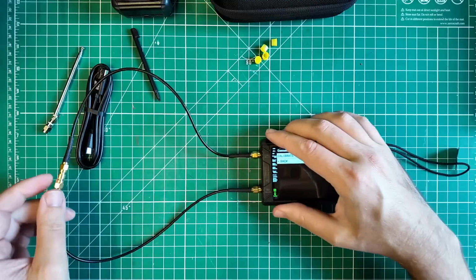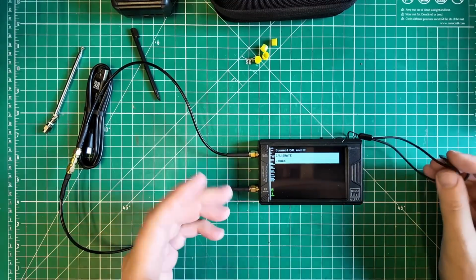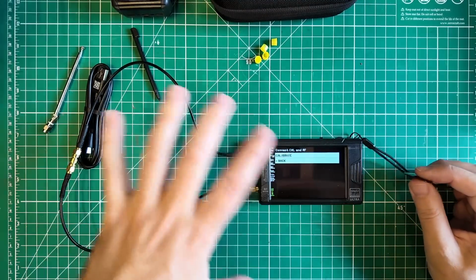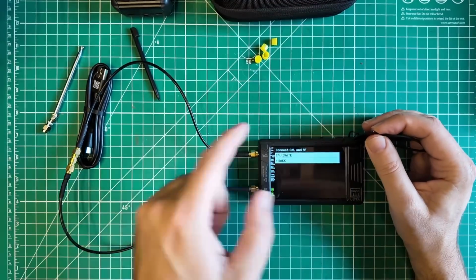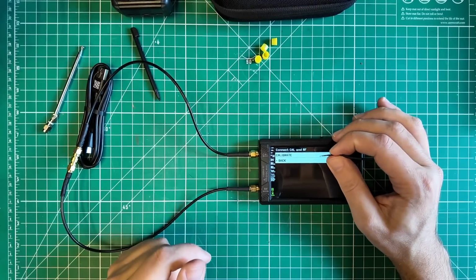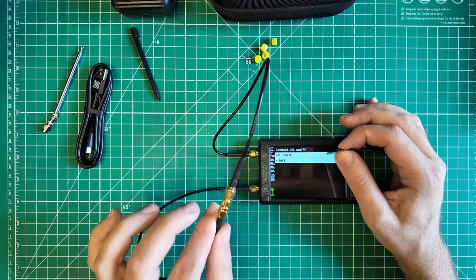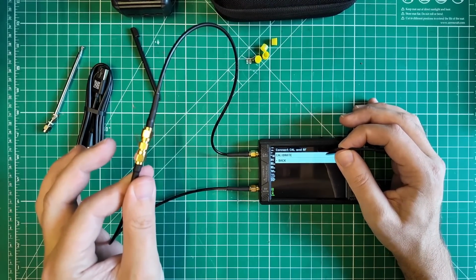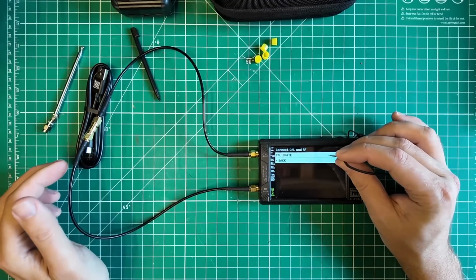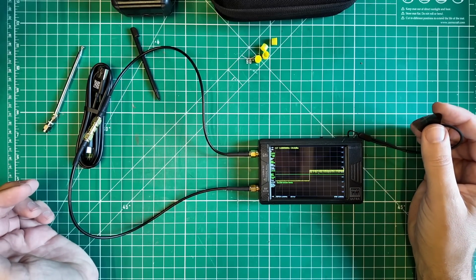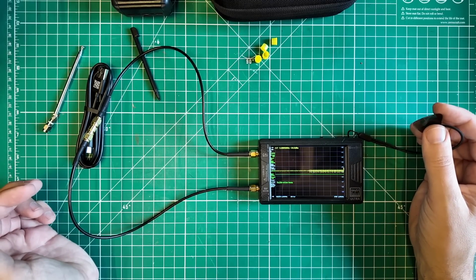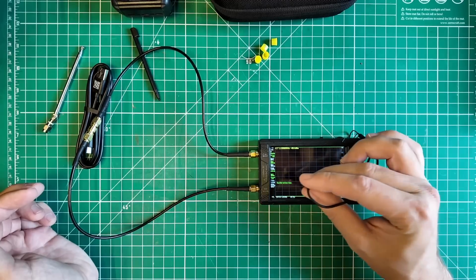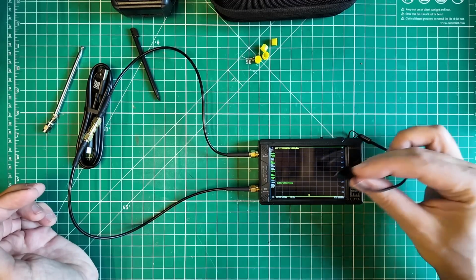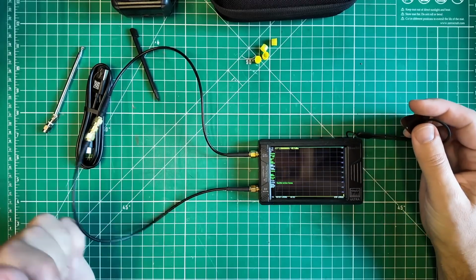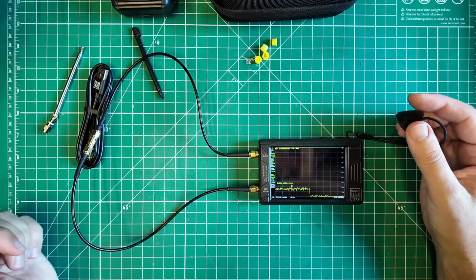And if you really want to get serious about it, then get the right gear in order to be able to calibrate it out. So connect Cal and RF, that's the Cal port, that's the RF port. They're connected through the two leads and the union. So hit calibrate. Now it's doing a bunch of stuff, running a bunch of tests, putting up a bunch of screen candy. Calibration busy, so don't stop yet. And you can see a little green line going across the bottom that shows you that it is still working.